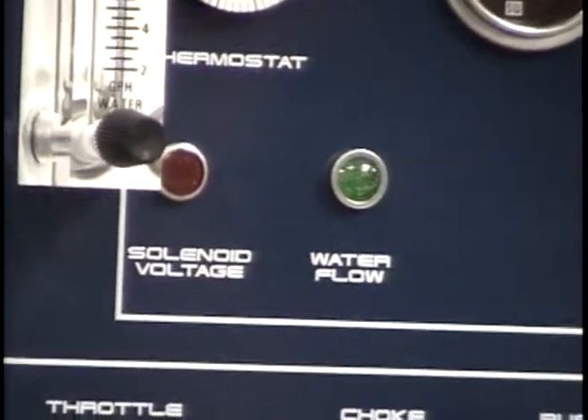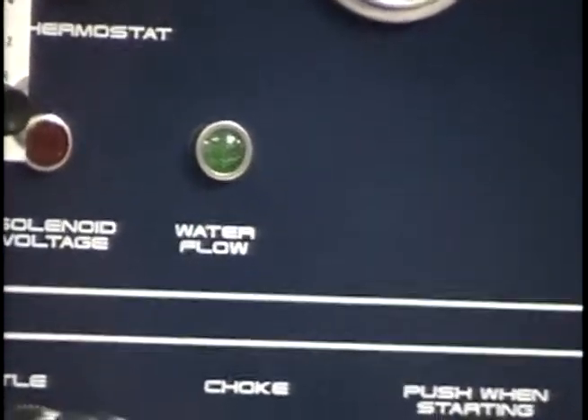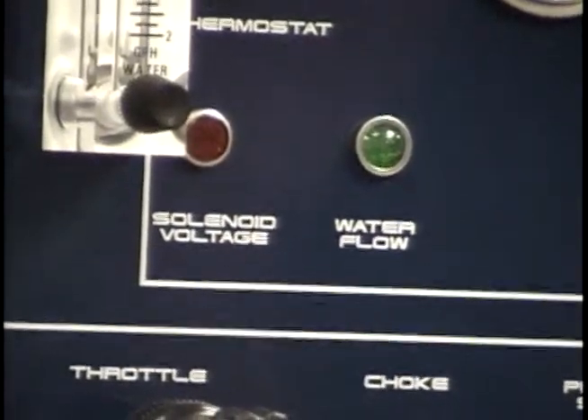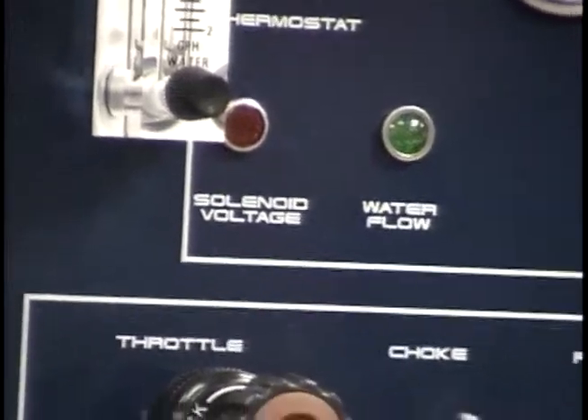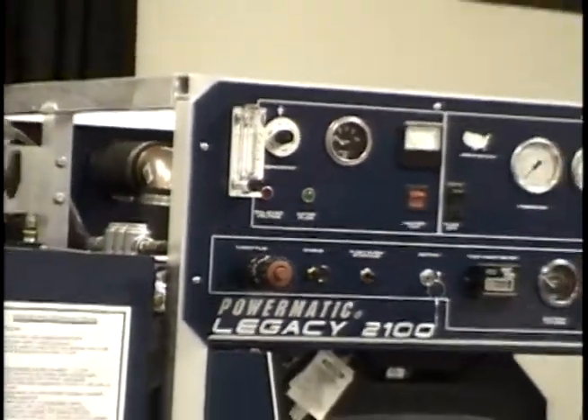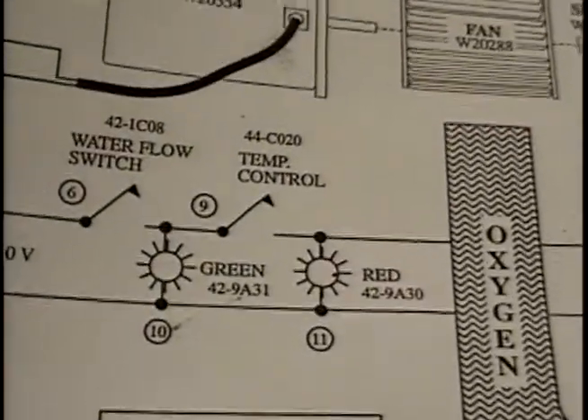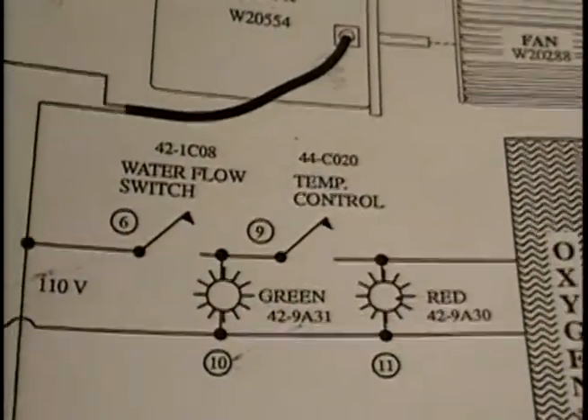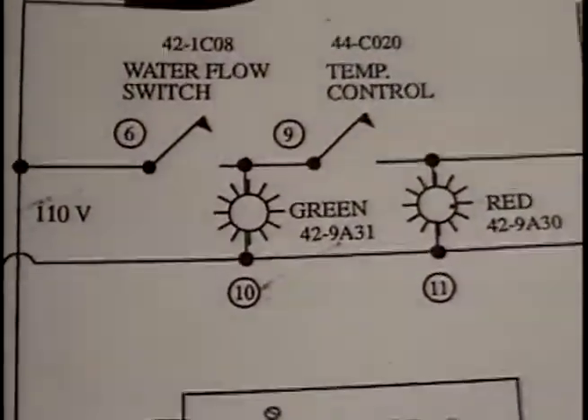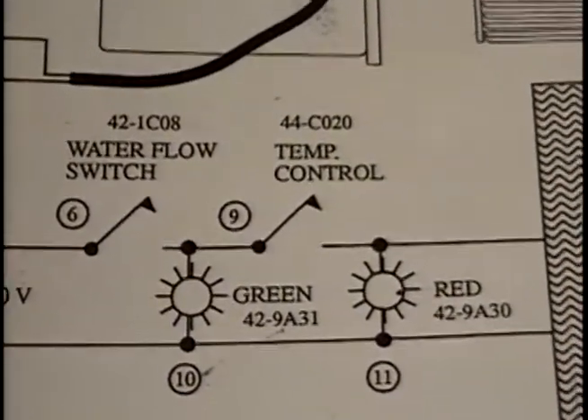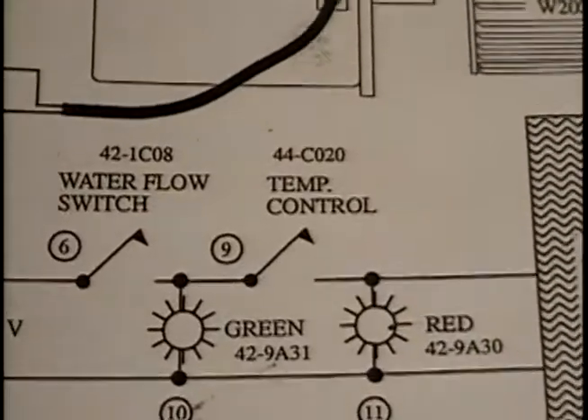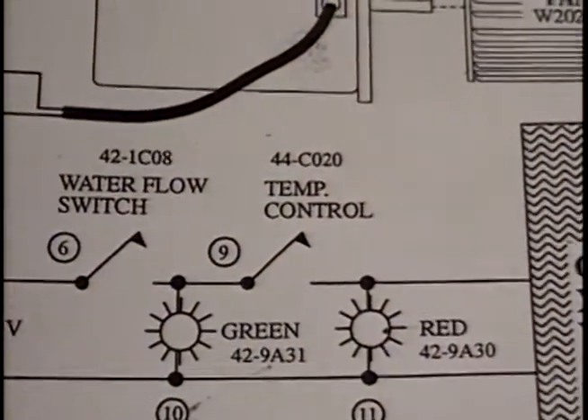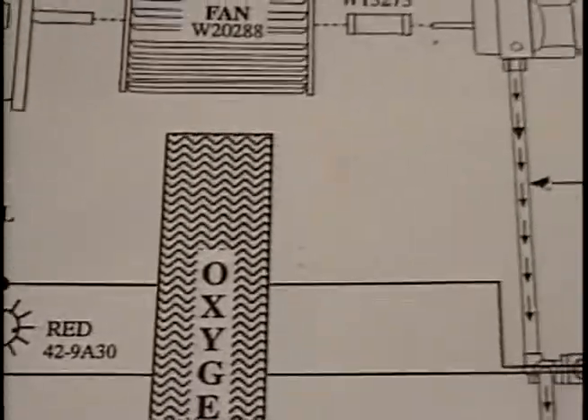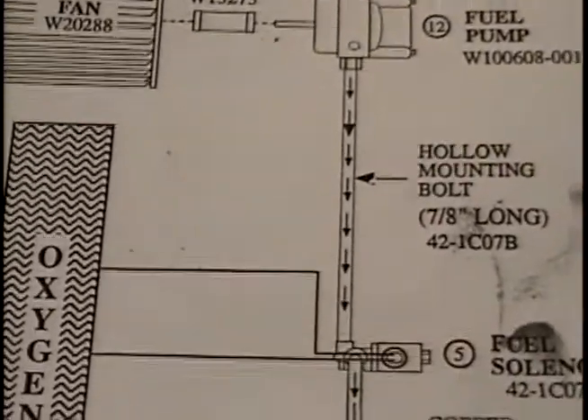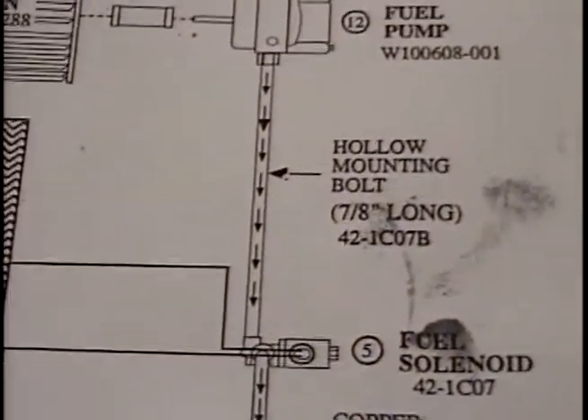What's the other requirement to get power through to the solenoid? What's that other switch? Temperature control. We turned this heater switch on a long time ago already. Now, once we get through the water flow switch, we turn on the green light, but there's still one other switch that has to be closed. You get the red light on, and when that happens, you've got power coming all the way over to the solenoid. The solenoid snaps open, and I've got my fire, I've got fuel into the fire.